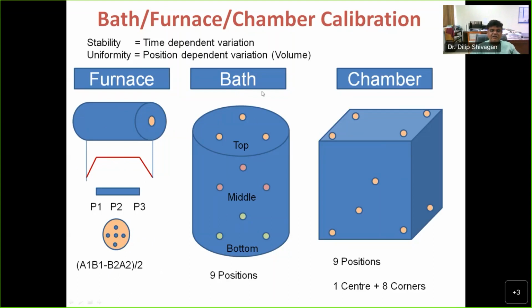Similarly for furnaces you can also use this AB or BA level strategy. For bath, depending on the height, you can measure at 9 locations, 3 at the bottom, middle, and top, and you can evolve the uniformity, while the middle point gives you the stability. For chambers, you also need 9 positions, one at center and others at corner. But for large storages, even the areas are very wide, so there are some EN and other standards where you can use 21 or more thermometers at different locations.